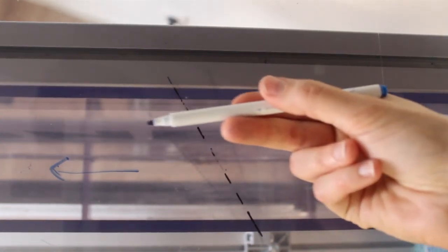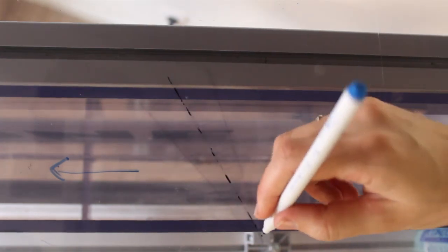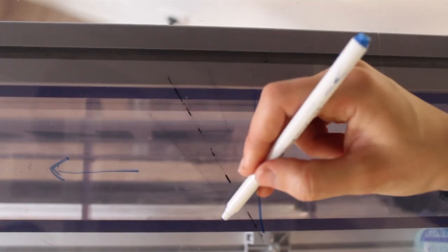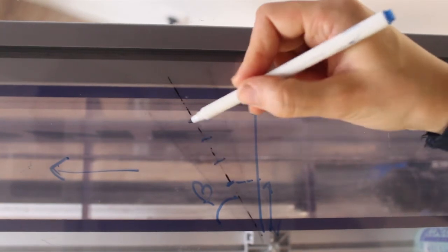As you know, or soon will learn, with the UVP technique, to get the flow velocity, the user has to measure in the flow axis, which is often complicated, or in an oblique direction to the flow, as in our example. And as it is sometimes practical to have the position along the perpendicular axis to the flow or flume, some user interfaces propose to indicate the Doppler angle beta.